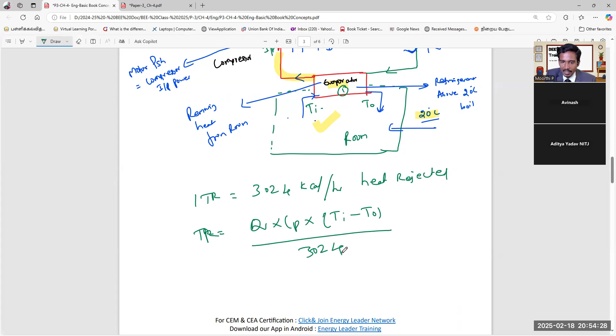Okay, then the formula: TR formula equals mass Q into Cp into delta T, so Ti minus T out, divided by 3024. That is the formula, it is a very important formula.